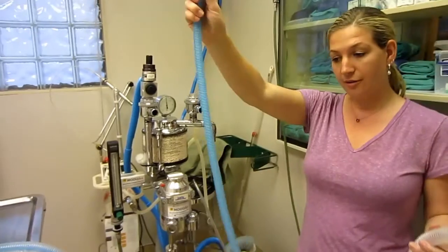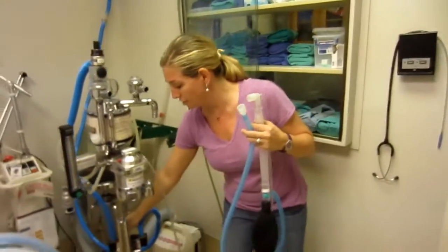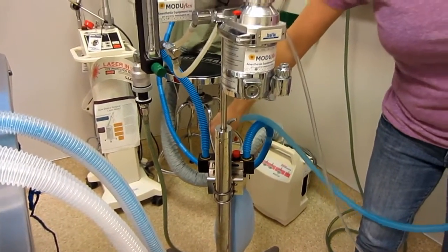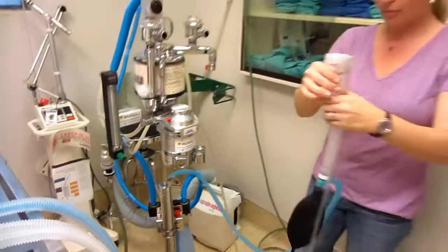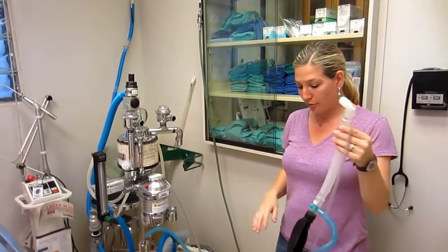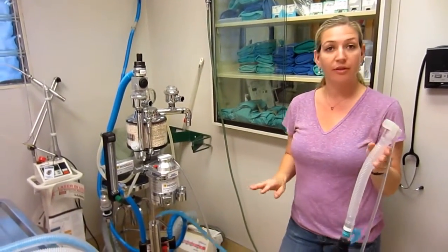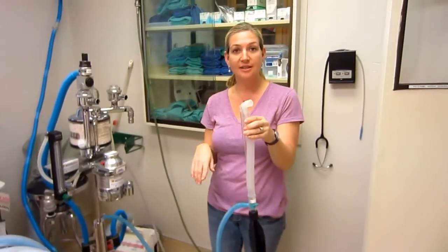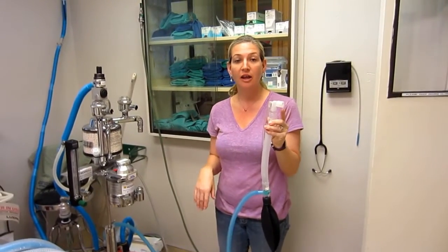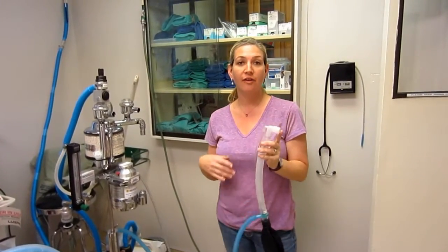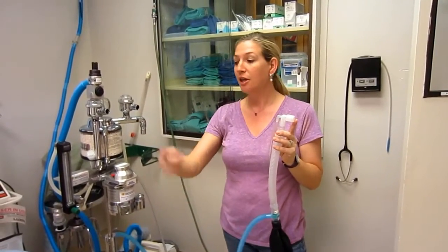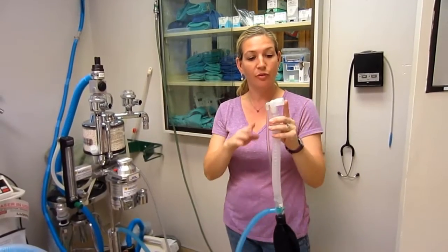The next thing I'm going to do is, this is our exhaust. So I've got to connect this to our exhaust or our scavenging system. So how this works is a little bit simpler than the rebreathing. Now this is not a circular breathing. Exactly as it states, it's a non-rebreathing. This is for animals that are small enough, they probably do not have the strength in their lungs to actually produce an exhalation that would utilize a rebreathing. So this makes breathing a little easier.